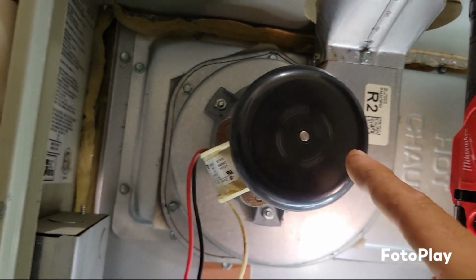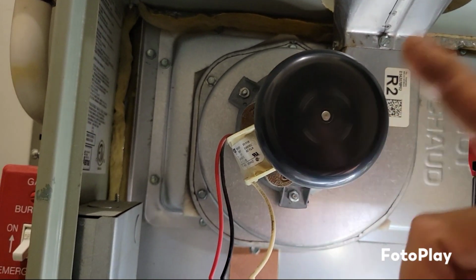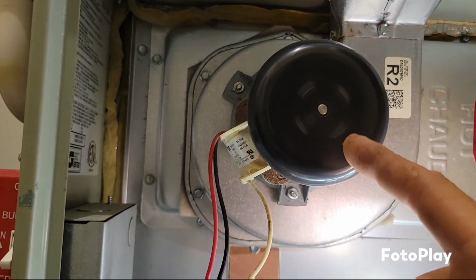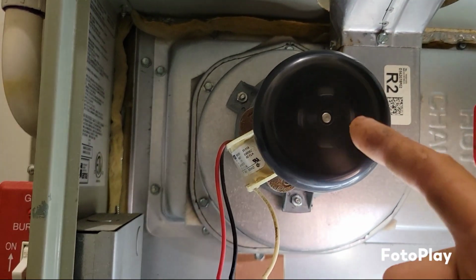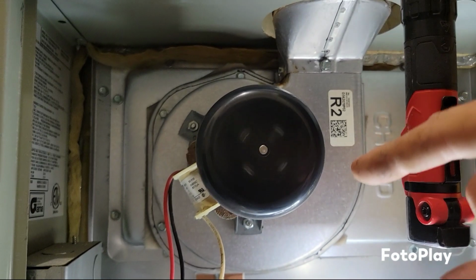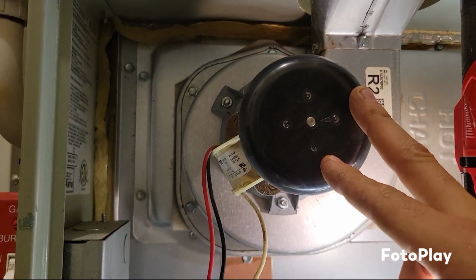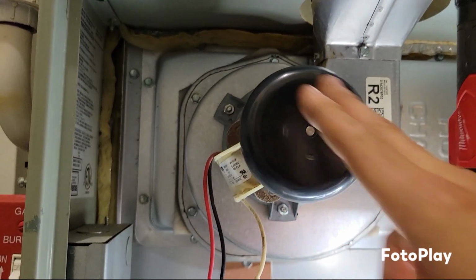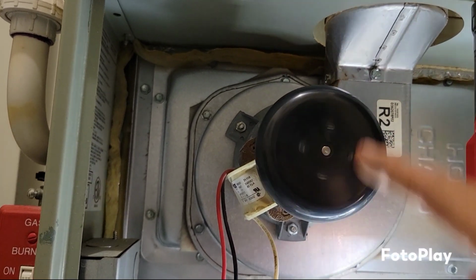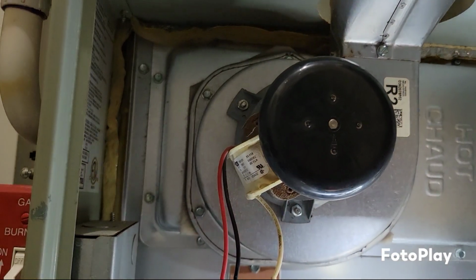So right now, this tells me two things. The motor is not stuck. The bearings seem to be okay. The blades aren't caught on anything. There's no bird that flew into the exhaust pipe or anything like that. So this tells me, for lack of a better way to say it, that this is fine. Like, we have good rotation here in the motor.